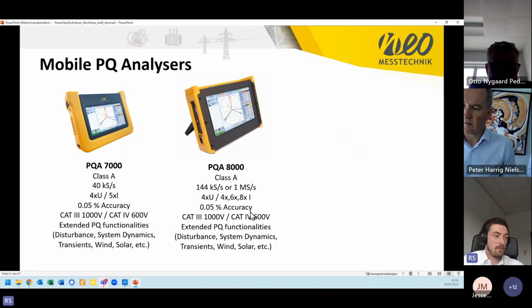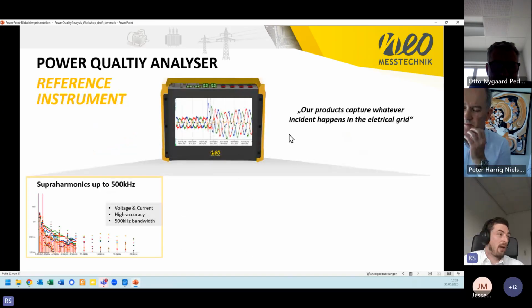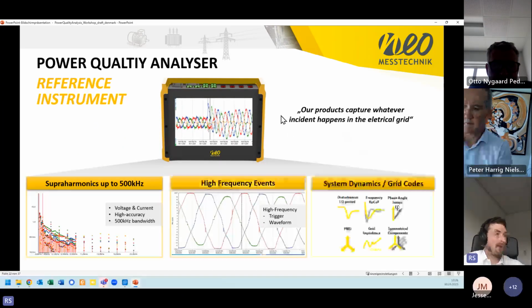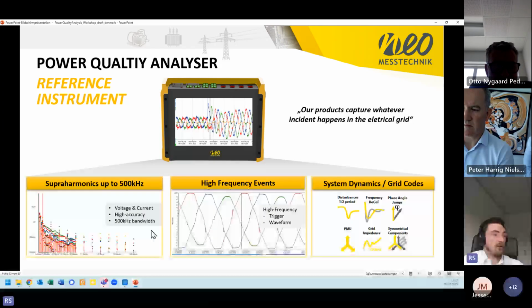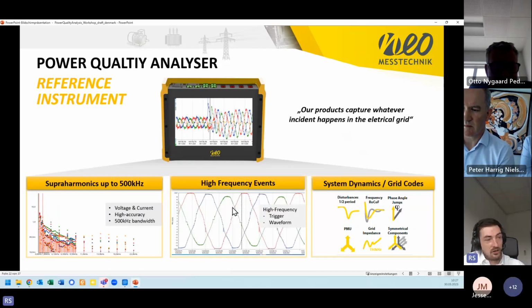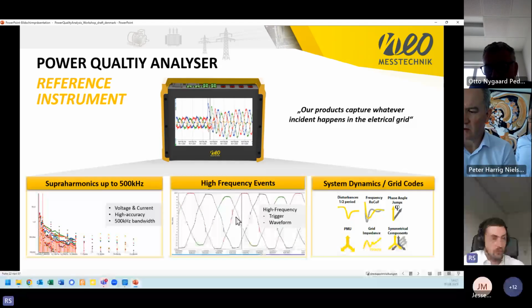0.05% accuracy here also. Safety category the same. Also here the extended PQ functionalities. So if we talk about the future power quality analyzers, we see supraharmonics even up to 500 kilohertz for voltage and current actually. And we have high accuracy, 500 kilohertz bandwidth. We see also switching operation, high frequency events in the current waveform. So we have also envelope trigger. So envelope trigger to cover these events, therefore also doing the FFT actually. And also vector scope can be shown in the analysis during this event.